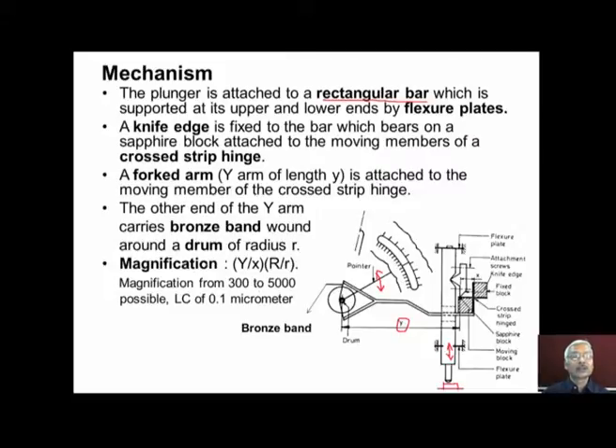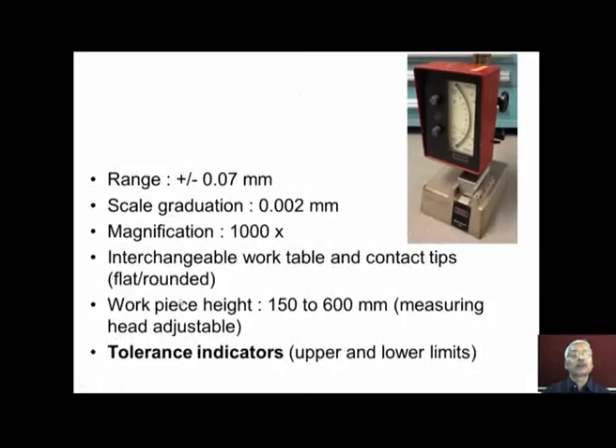The magnification can be calculated using this expression: Y divided by X, times R upon r. Y is the length of the forked arm and X is this distance, where R is the length of the pointer and small r is the drum radius. The magnification possible with such a comparator varies from 300 to 5000, and a least count of 0.1 micrometer is possible. Now the specifications of the commercially available sigma comparator are as follows.